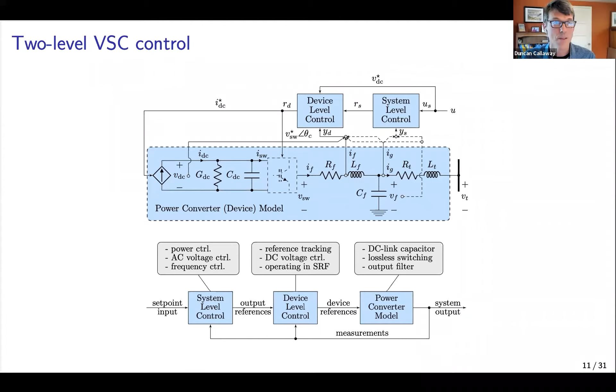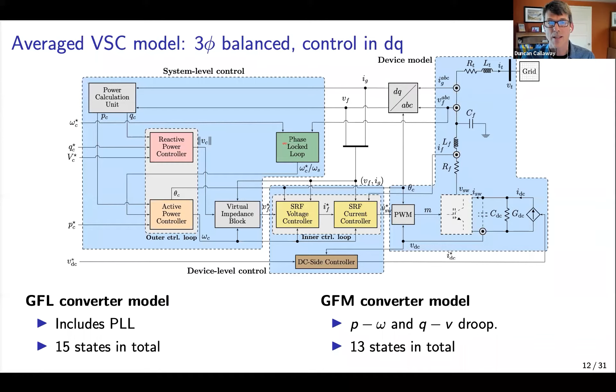So let's go ahead and look at that in a slightly more detailed version of a voltage source converter model. We use a 3-phase balanced representation, so we assume everything is balanced. Here you can see in this blue area we've got a system level control block. In this blue area here, we've got device level. And then over here, we've got the physics of the device itself. So once again, you can see voltage and current control, reactive and active power control sitting in these two major blocks. And we're going to be asking how each one of those blocks contributes to instabilities when they arise. We've got a different model for a grid following converter as well as a grid forming converter. The key difference between the grid following and the grid forming is this phase locked loop. Remember I said before, a grid following converter has to be connected to the grid to work, and that's because it senses that grid frequency and then basically reproduces it. And this is what that phase locked loop does.